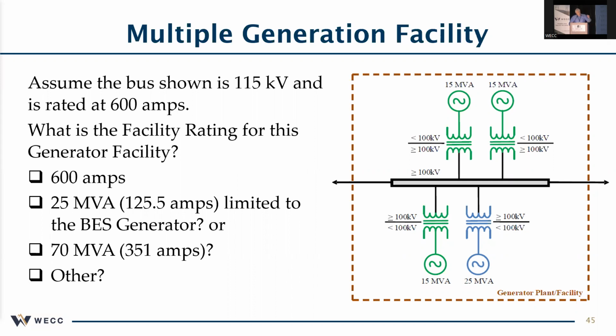But you could justify with the methodology almost any one of those answers, depending on your perspective of who the owner is, what the facility was, and how you're considering that other generation. I know a balancing authority would want to know what they can get out of that whole generating station. Doesn't matter to them whether it's a non-BES, they still want to know what they can dispatch and what's going to be serving load. A transmission operator might be interested in the current carrying capability of that connection line there, the 600 amps. So something to keep in mind.